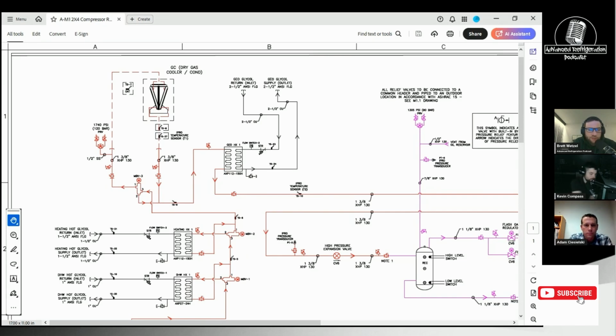I wonder if it'll ever get to a point where they're going to do dual set points like you do for a case controller, because people ask me that. We've had conversations about why the United States has such a problem a lot of times with the ambient thing and CO2. My thought is, okay, up in Canada, we have 2 different temperature bands. In the United States, we have several, right? And so they all react a little bit differently, and a rack that works down in Texas is going to be different than a rack working up in Chicago.